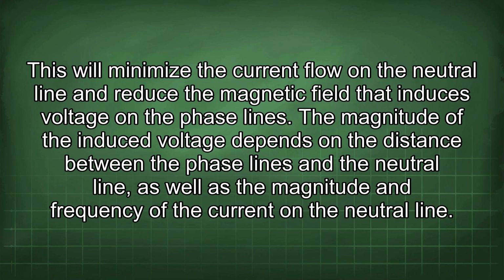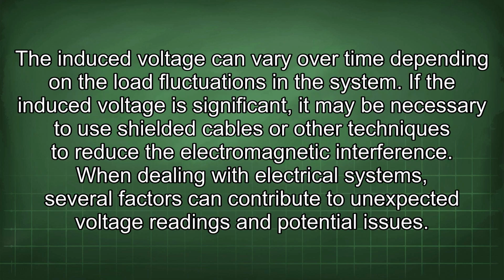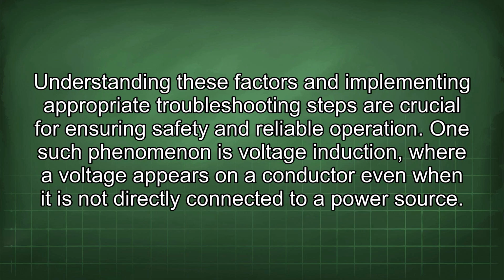the phase lines. The magnitude of the induced voltage depends on the distance between the phase lines and the neutral line, as well as the magnitude and frequency of the current on the neutral line. The induced voltage can vary over time depending on the load fluctuations in the system. If the induced voltage is significant, it may be necessary to use shielded cables or other techniques to reduce the electromagnetic interference. When dealing with electrical systems, several factors can contribute to unexpected voltage readings and potential issues. Understanding these factors and implementing appropriate troubleshooting steps are crucial for ensuring safety and reliable operation.